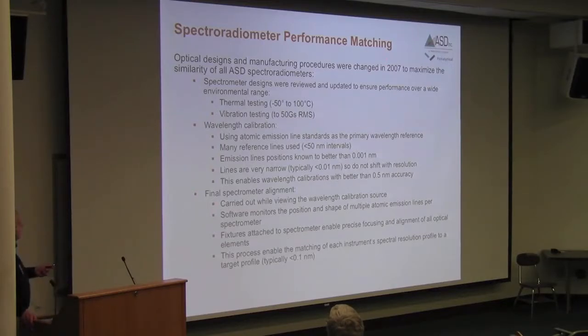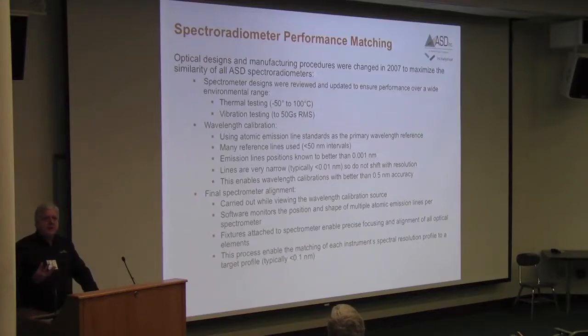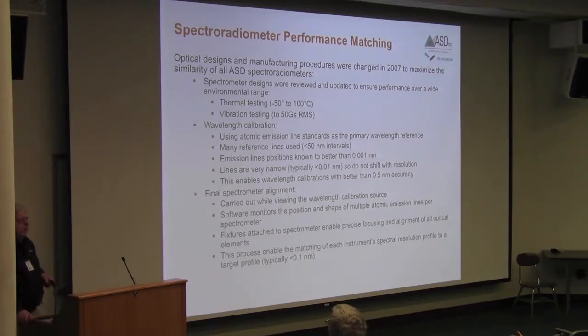And really prior to 2007, we had specifications for instruments. So let's say a FieldSpec standard resolution had a specification for 10 nanometer resolution, but when you were building the instrument, the instrument would get focused, the grating, would do all the alignment, the focusing of the optical elements. And if we got higher than 10 nanometers, that was okay. It was always sort of a one-sided specification. It had to be 10 nanometers or better in order to pass the spec. The problem with that is you ended up making instruments where the resolution profile, while it met the spec, could be better than the spec, because from the remote sensing standpoint, more spectral resolution is better.